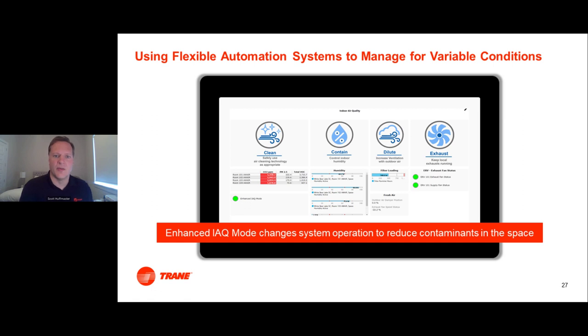Another thing that you can see is, what if we've got some variable conditions, right? So it's not always just the data that you're seeing inside the building that might lead to a decision for how you control your system. It could be also other data. Think about, again, we're in a pandemic today. Pandemic means, the way ASHRAE terms it, epidemic conditions in place. So what if we've got systems where we can balance taking different action if we have different metrics leading to that? So if case rates are high, and even as we get to endemic, if flu cases are high or COVID becomes endemic this coming fall of 2022 and we start to see case rates go up, wouldn't it be great if we could toggle our system from focusing on optimizing around energy use, and instead we're going to have enhanced IEQ mode?